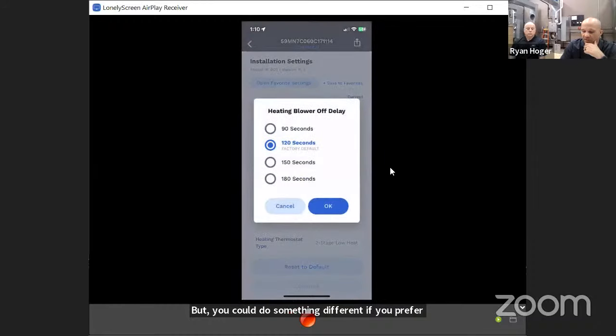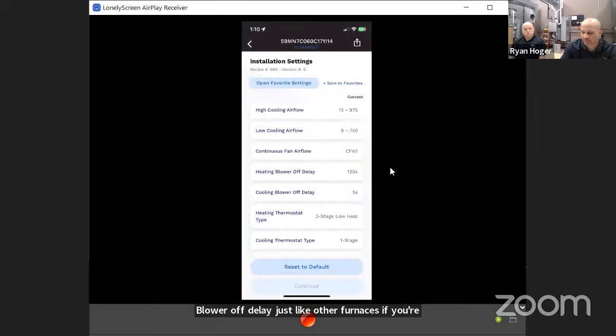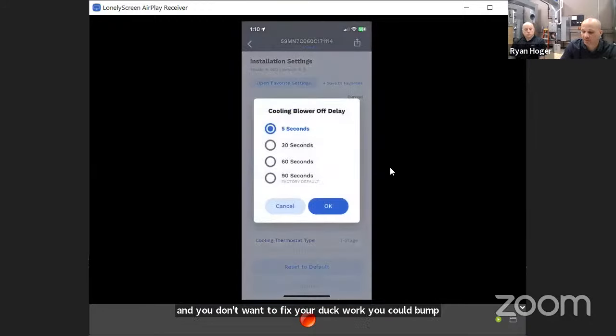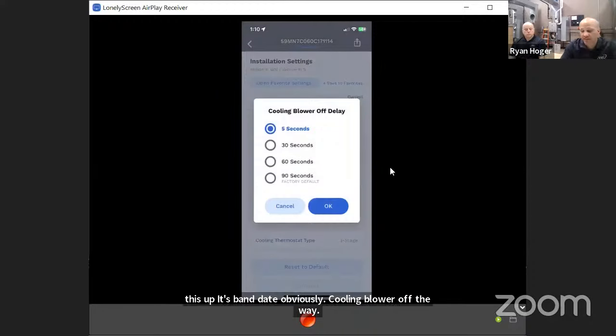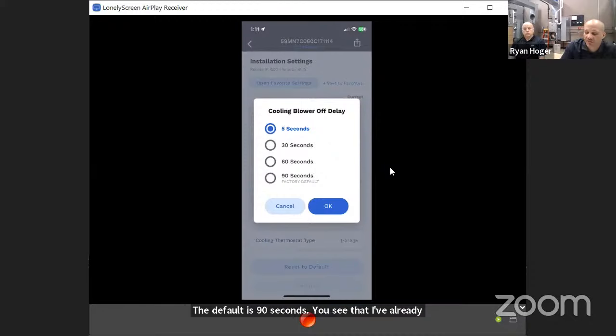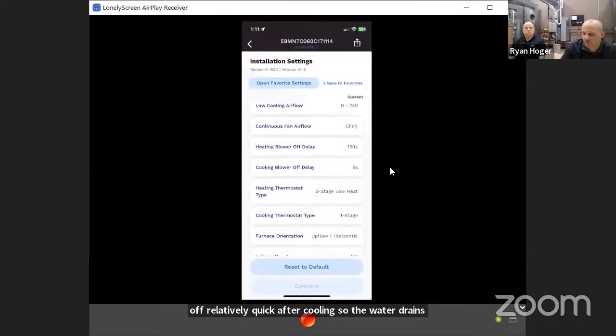Blower off delay, just like other furnaces. If you're having high limit trips because your ductwork sucks and you don't want to fix your ductwork, you could bump this up. It's a Band-Aid, obviously. Cooling blower off delay. The default is 90 seconds. You see that I've already changed this one to 5 seconds. I like the fan to shut off relatively quick after cooling so the water drains off the coil and doesn't re-evaporate into the air. Totally a preference thing. Nothing's going to break either way.